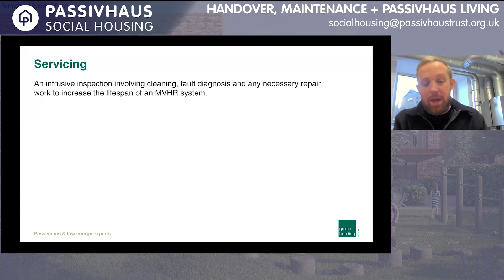Servicing, so this is quite an intrusive inspection and cleaning by someone experienced. So it does need to be someone experienced doing this for yearly servicing. There's our experienced person, Rick. Most manufacturers do suggest 4 years to keep on top of it. And that'll include removing and cleaning the heat exchanger, cleaning the fans. So even with the filters, you will find that after a few years, you start to get some fine particles building up on the internal components, just very fine dust.